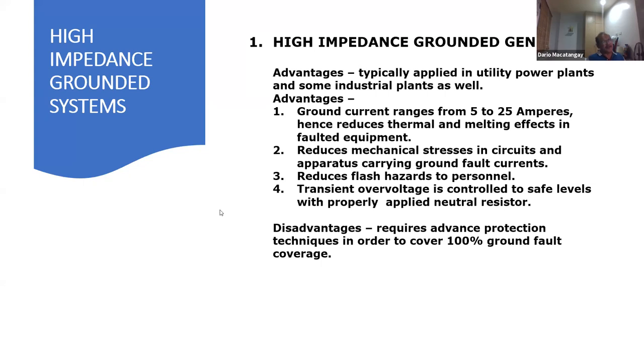There are four types of fault here. We have the three-phase fault configuration, the phase-to-phase fault, the phase-to-ground fault, and the fourth one, which is the double line to ground fault. Now, if the manufacturer designed a generator for a three-phase fault configuration, and the line to ground fault exceeds the three-phase fault, then the generator could be damaged. So typically we use the high impedance ground system because in a power plant, the line to ground fault current is higher than the three-phase fault current.